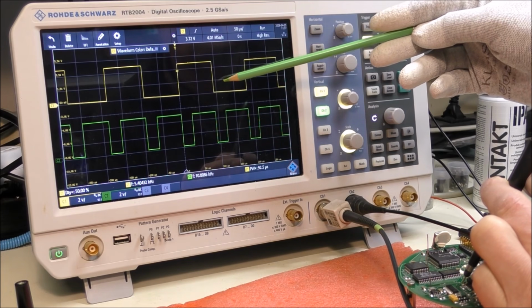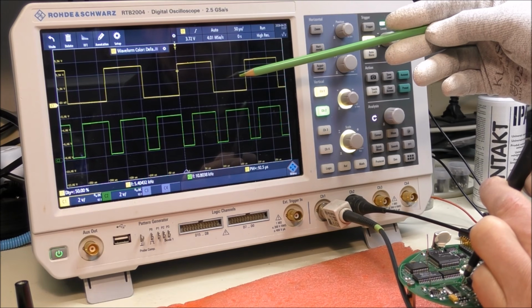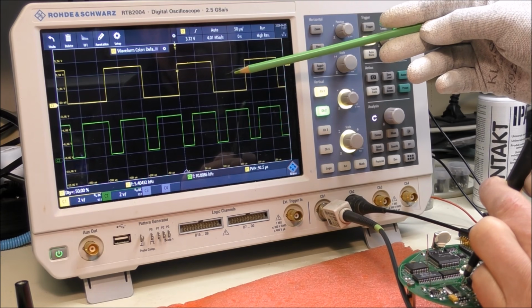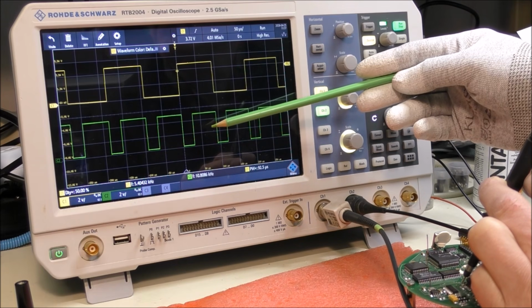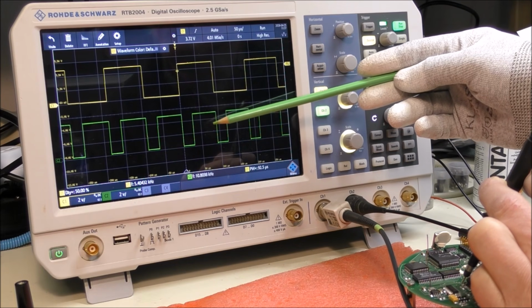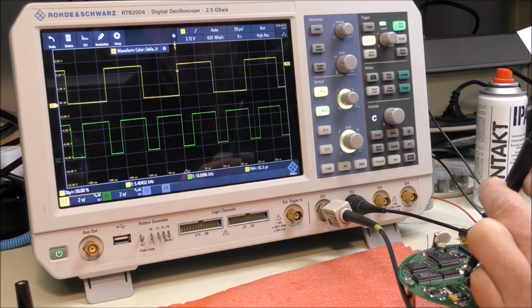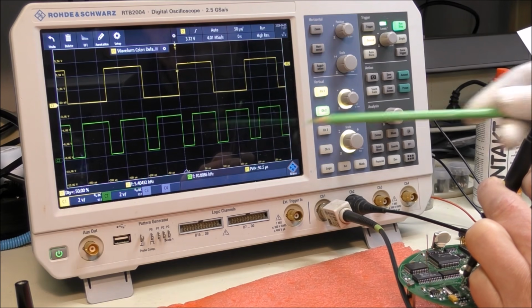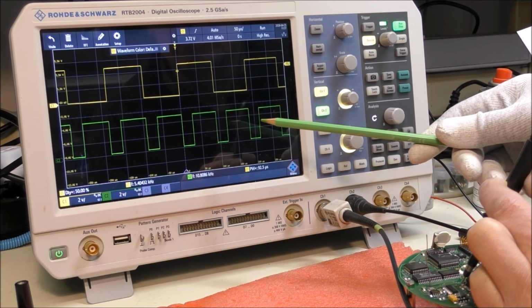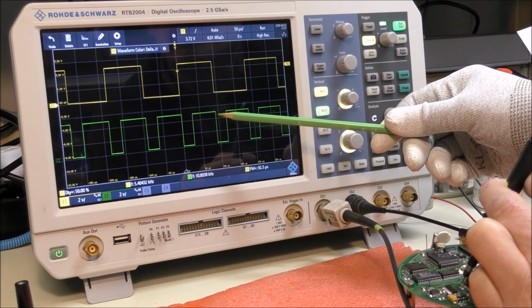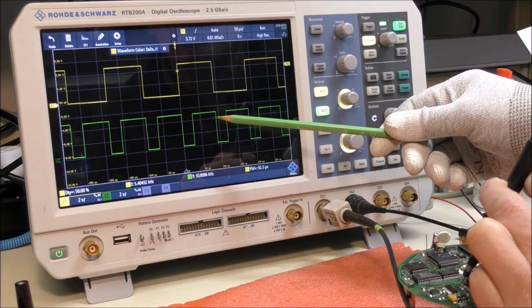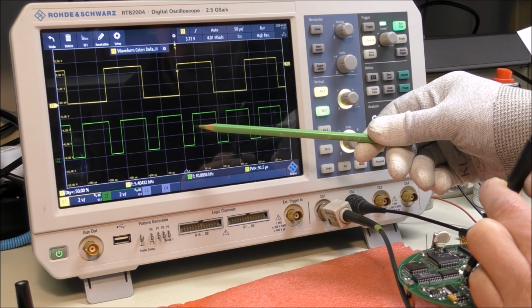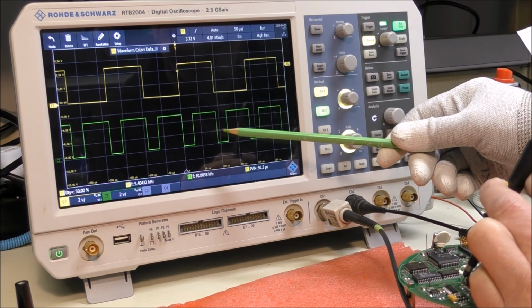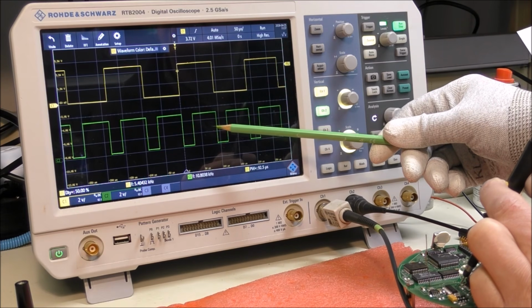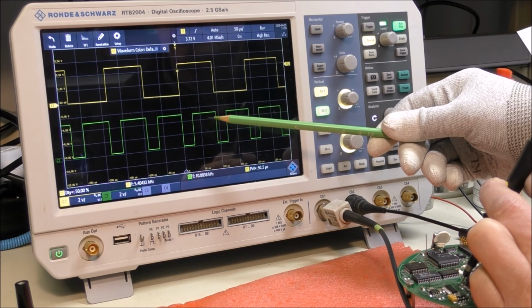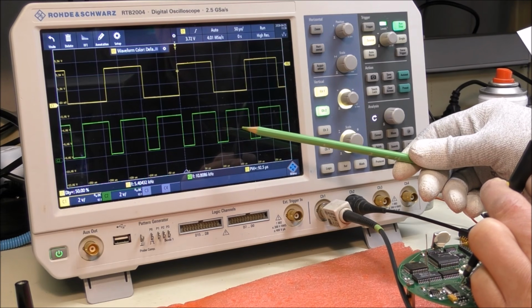We can see on the screen the reference signal for the excitation. This is the square wave, 50% duty cycle. Frequency is 5.4 kHz. And we have here the reference signal for the phase detector. The frequency is twice this frequency, approximately 10.8 kHz. We can notice that the duty cycle is not exactly 50%. I guess that the duty cycle is set in order to adjust the phase of the fundamental of that signal in order that this fundamental is in phase with the second harmonic of the sensor. This permits to increase the sensitivity of the detection.